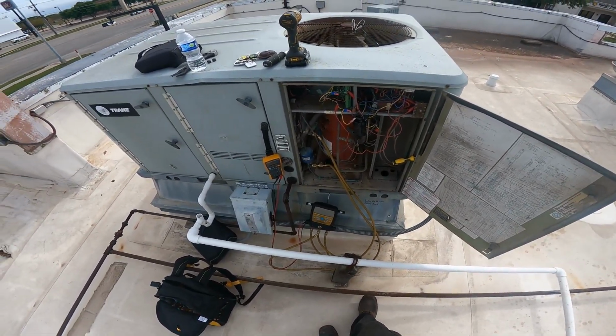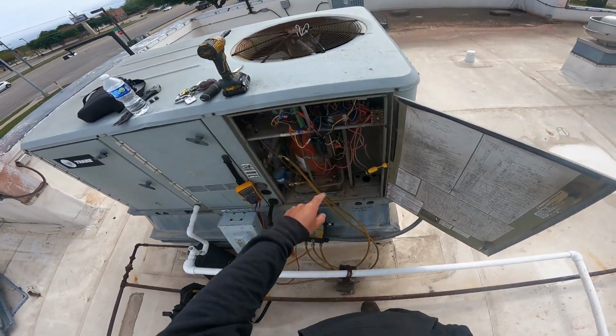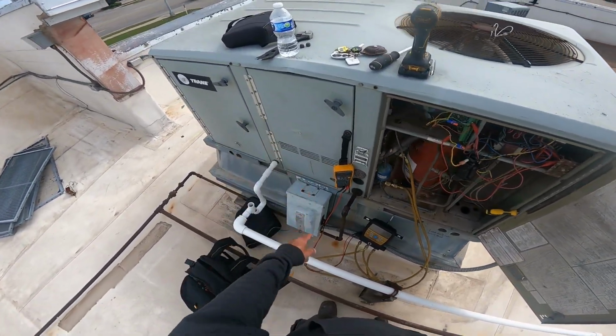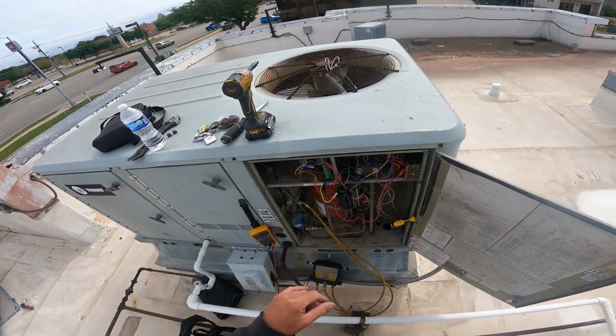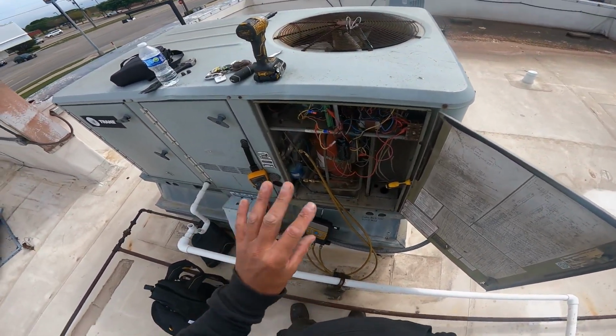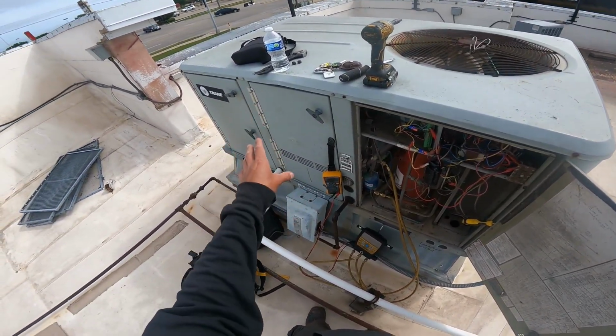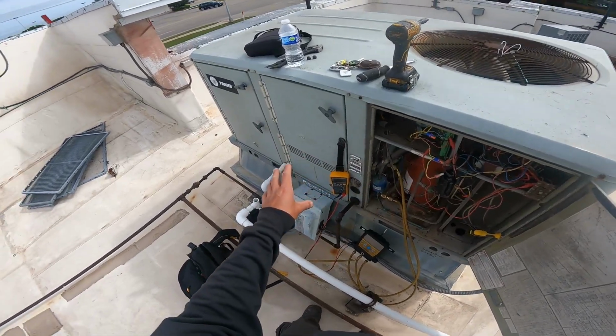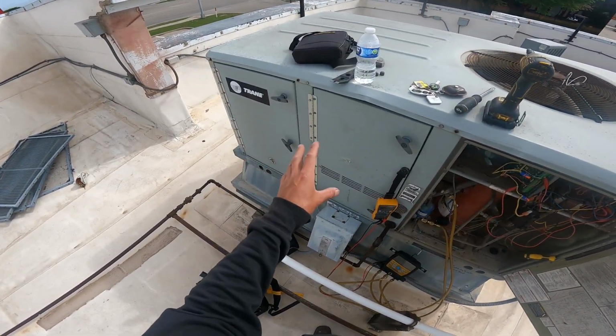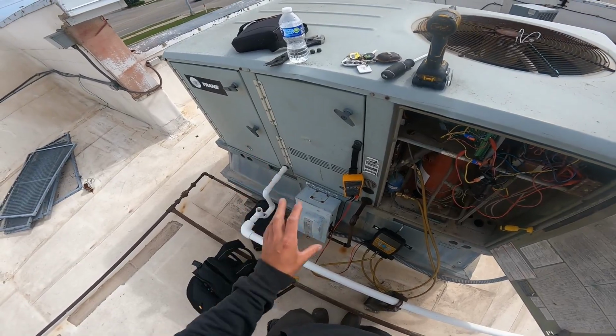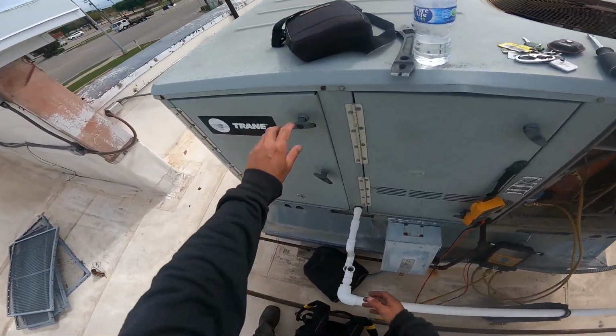Blower works, condenser fan works. We need a new control board, a new inducer motor, and a new heat exchanger. And that's just assuming we don't have a leak, we're not low on charge, and our header assembly isn't restricted, which is notorious with Trane, especially the older ones.